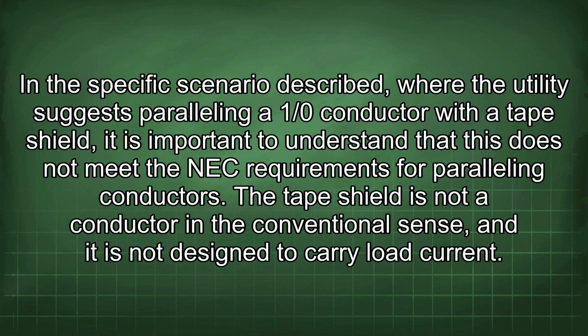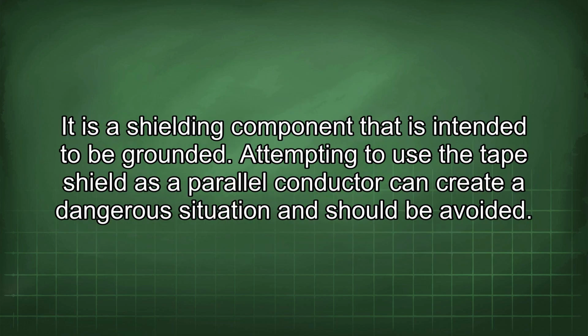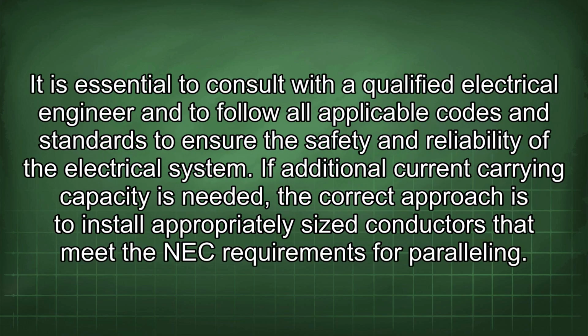These requirements are intended to prevent uneven current distribution, overheating, and other problems. In a specific scenario described, where the utility suggests paralleling a 1/0 conductor with a tape shield, it is important to understand that this does not meet the NEC requirements for paralleling conductors. The tape shield is not a conductor in the conventional sense, and it is not designed to carry load current. It is a shielding component that is intended to be grounded. Attempting to use the tape shield as a parallel conductor can create a dangerous situation and should be avoided. It is essential to consult with a qualified electrical engineer and to follow all applicable codes and standards to ensure the safety and reliability of the electrical system.